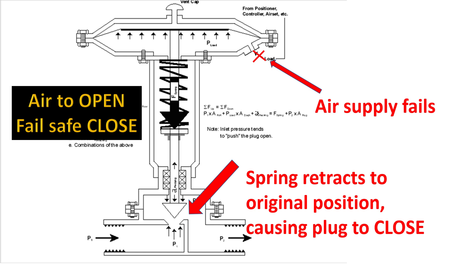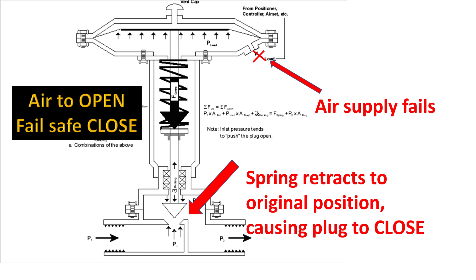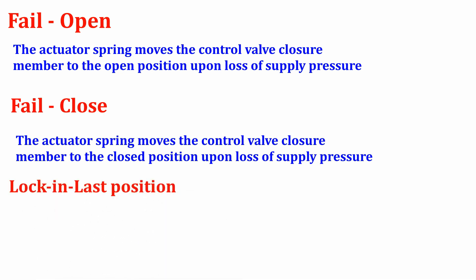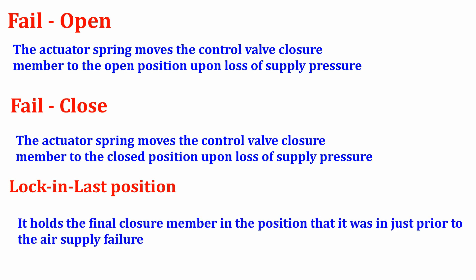Finally we have lock-in last position, which we shortly call LILP — that is, fail in place or stay put. In this mode, it holds the final closure member in the position it was just prior to the air supply failure. For example, if the control valve is maintained at 60% of valve opening and the air supply fails, the lock-in last position mode will remain at that same 60% open even during the supply failure.